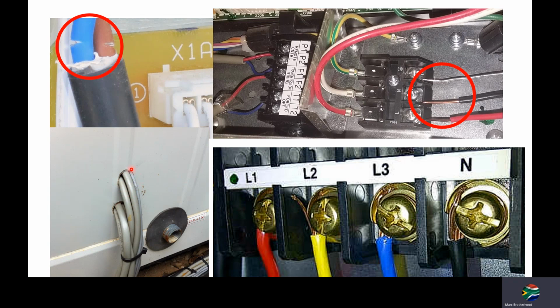Here you can see there's no grommets, so with time, these holes that have been drilled are just going to eat into the cables. Here you can see on a three-phase system, the installer hasn't used lugs. There's very poor contact area, and here you can see on your L2 phase, one of the conductors has already popped out. So this is going to increase current draw on the cable, resulting in it running much hotter.